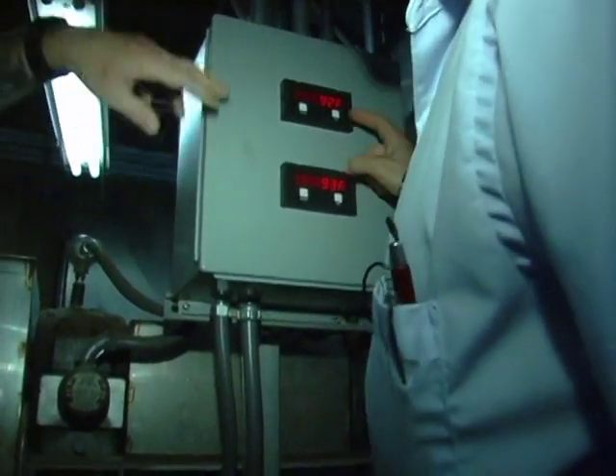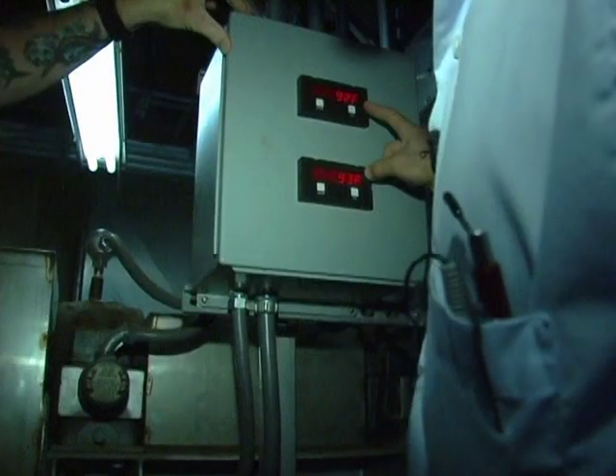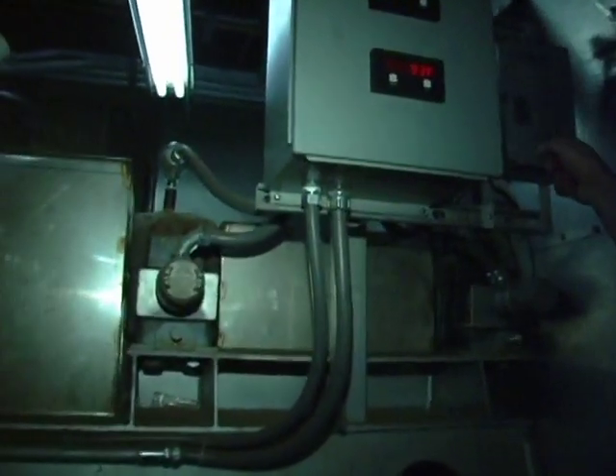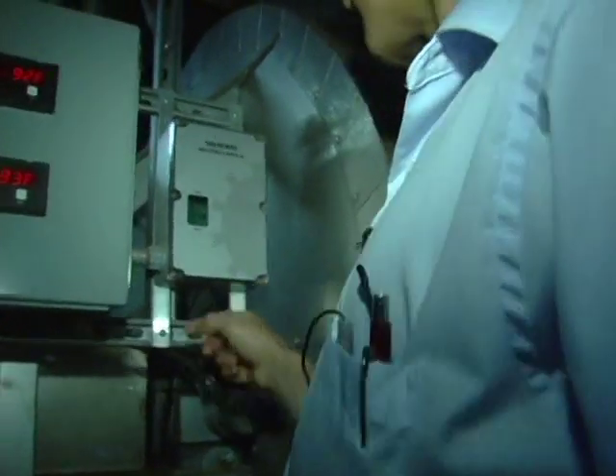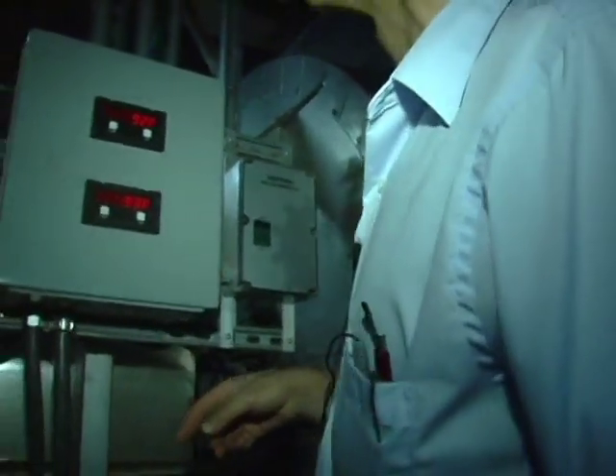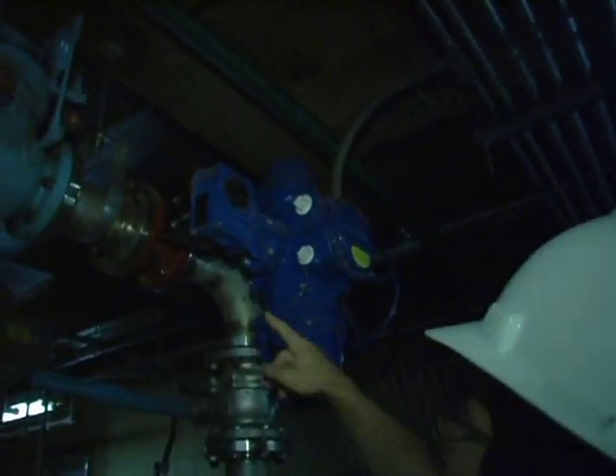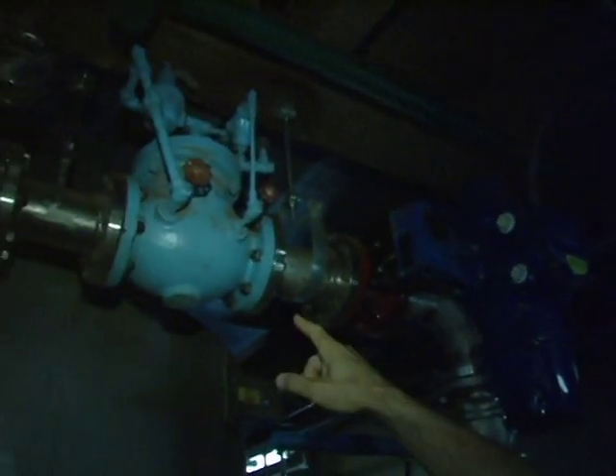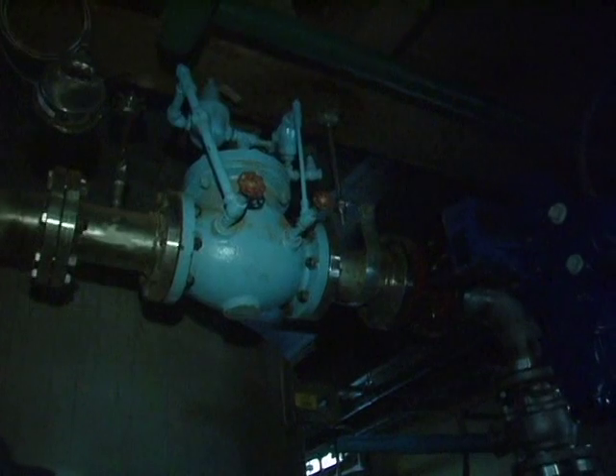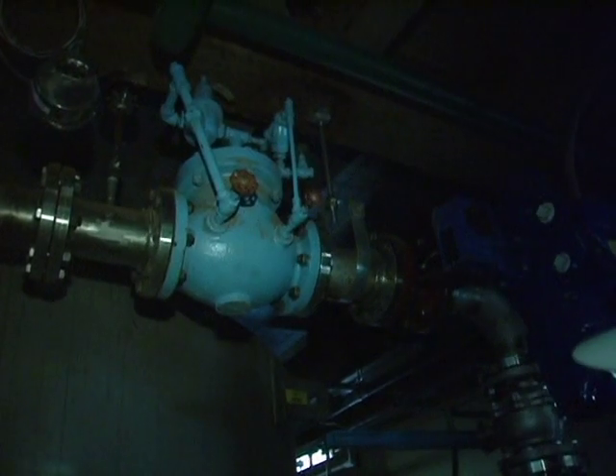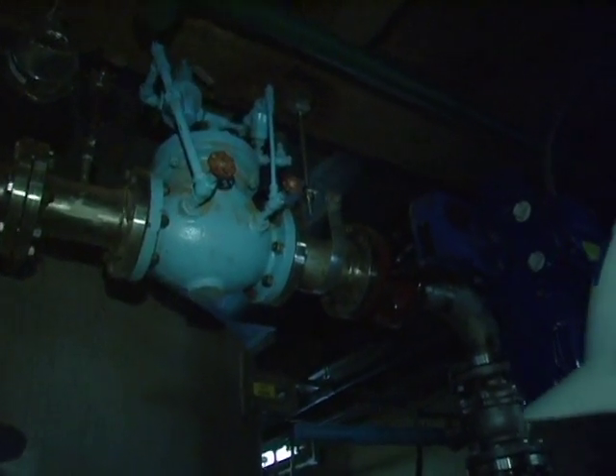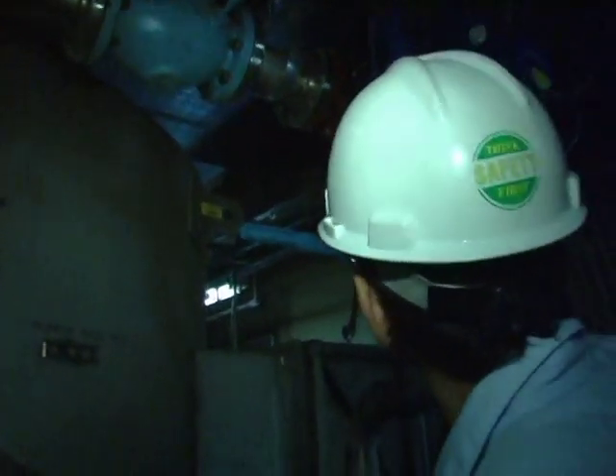Which ones are these? One's vibration or one's... These are both temperature. Oh, temperature. Two temperature. You got a vibration one right over here. Oh, okay. Vibration sensor, okay? So you got the vibration there. There's a control valve here, a limit torque flow control valve. Okay? That's a pressure reducing valve because they wanted to see so much pressure at the nozzles. They wanted to reduce it down. What's the setting like that? I think it's about 30 PSI. We got around 60 in here now, something like that. Oh, that's good. Yeah. And you got a manual shut-off valve here.